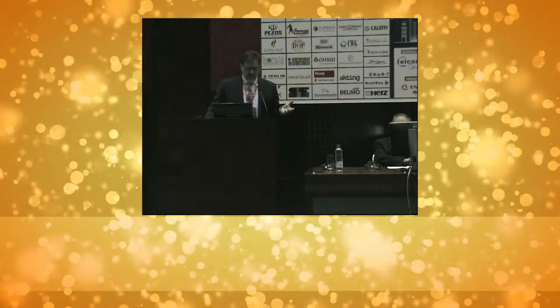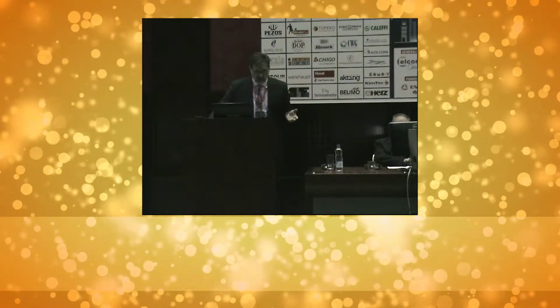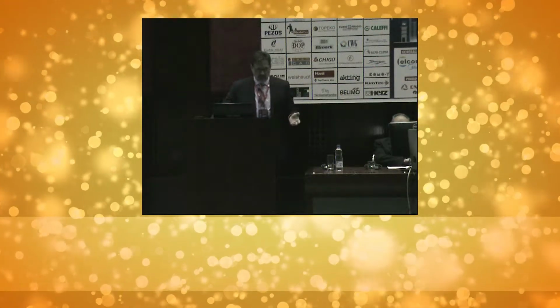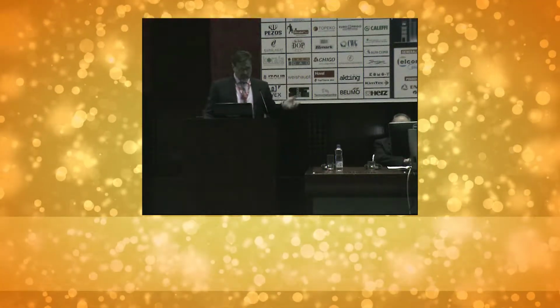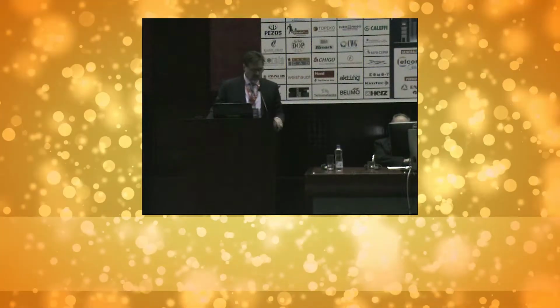Guideline number 3 is the maximum velocity, as I already said. That's very simple. Just remember you never exceed 2,000 feet per minute. When I was a student, it was 5,000, I believe, in Belgrade, which was ridiculously high. So the pressure drop was astronomical, and that's why the fans were big. So 2,000 you should limit. The less you go, the better it is.